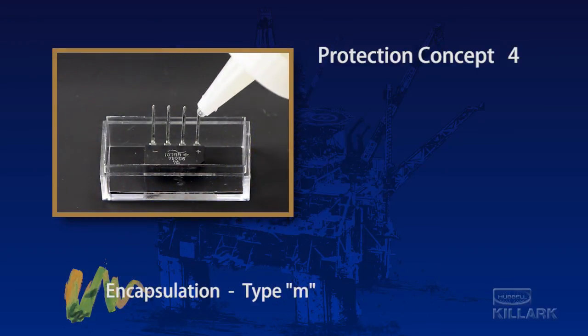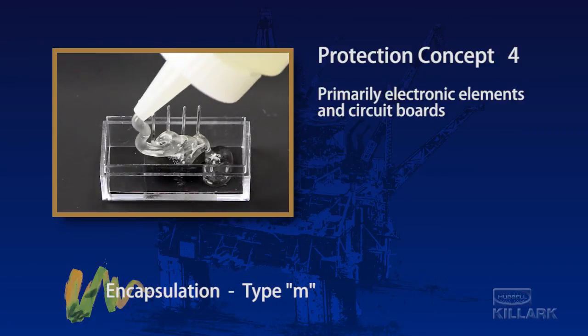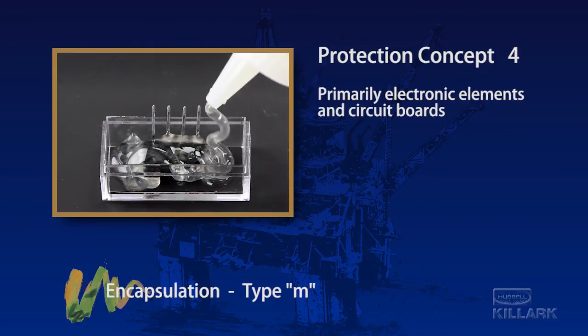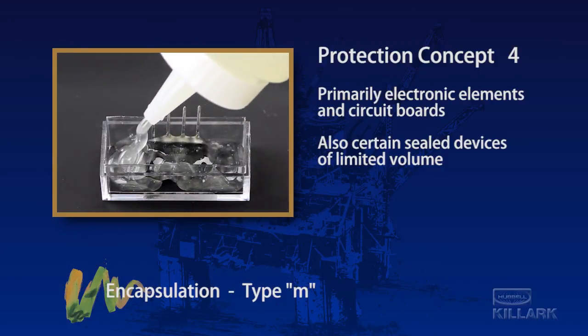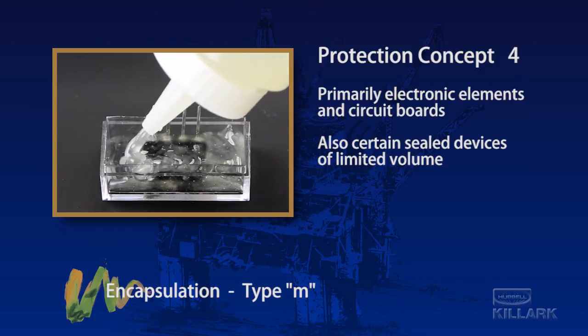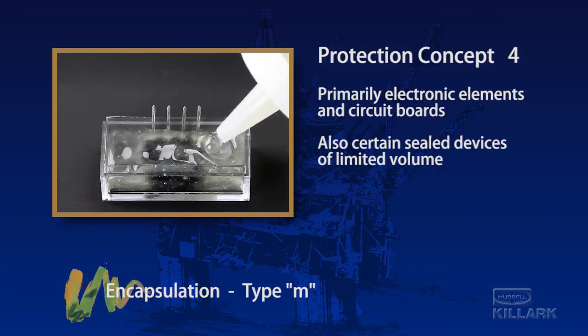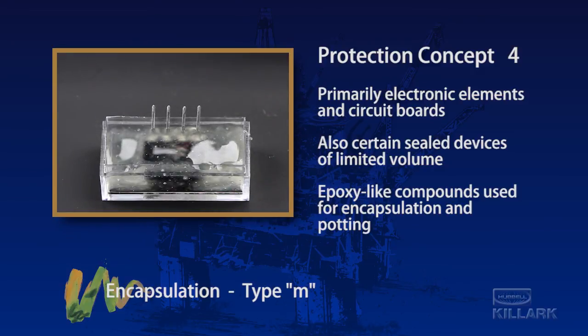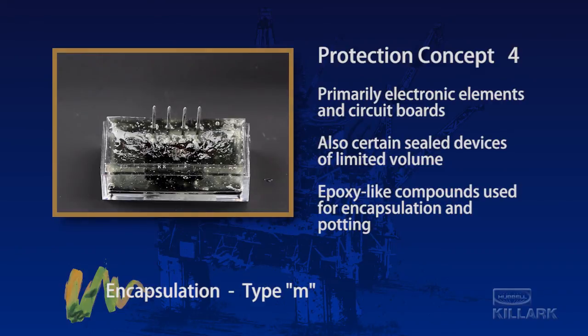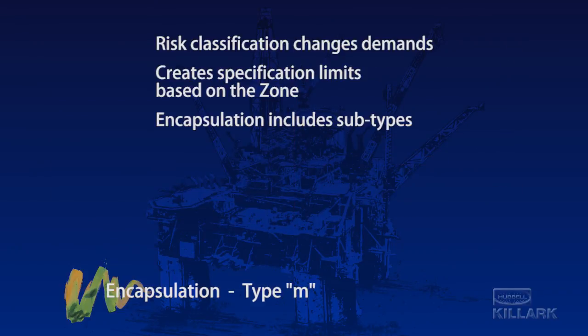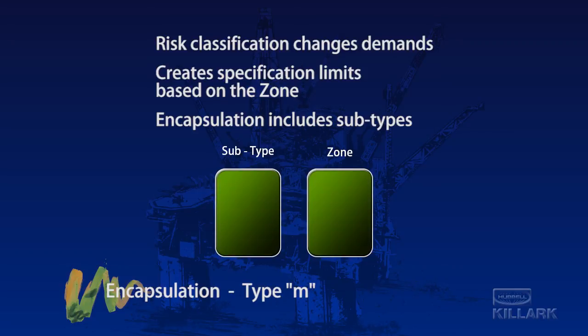Also within this concept is encapsulation, Type M, a fabrication technique that primarily provides protection for solid-state electronic components and several types of circuit boards. Certain sealed devices containing limited volumes with constrained temperatures may also be encapsulated. A variety of compounds, epoxy resin, for example, would be used in the initial fabrication process or in a potting procedure following assembly of the manufactured components. Similar to intrinsic safety, a second letter is used to identify the zone applications allowed for the equipment. MA is permissible for all zones. MB is for Zone 1 and 2, while MC may only be installed in Zone 2.